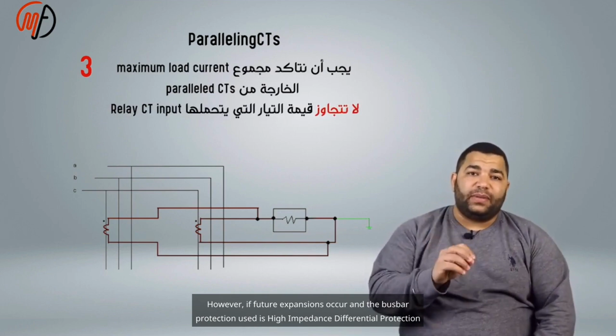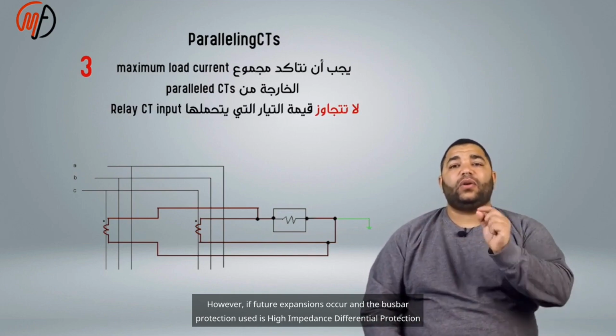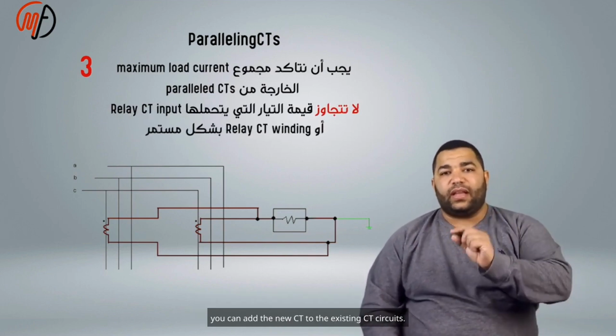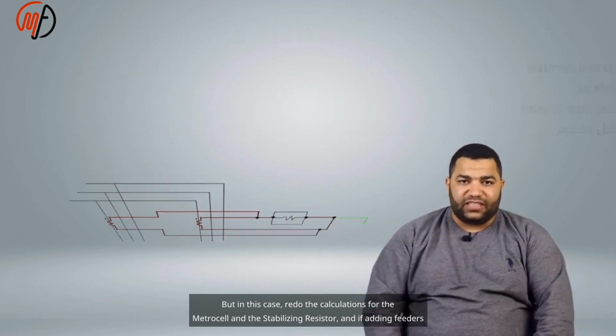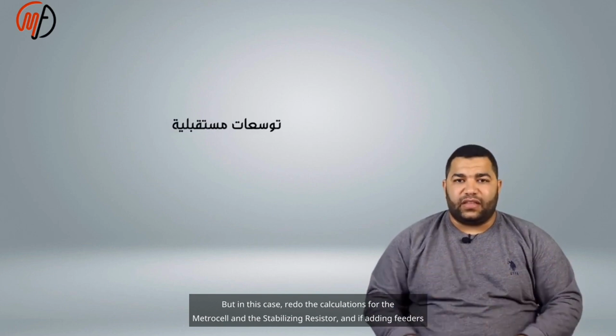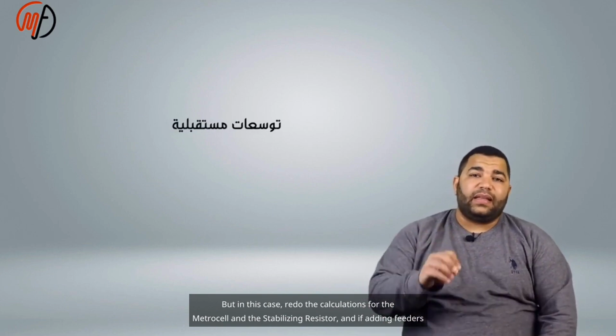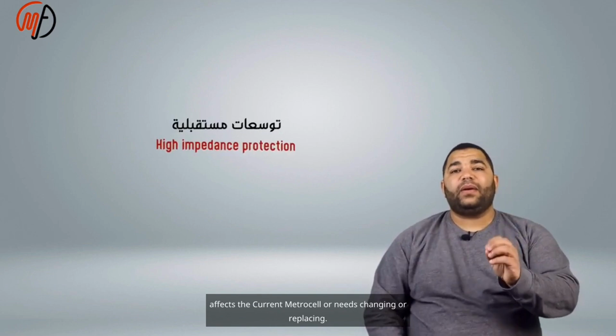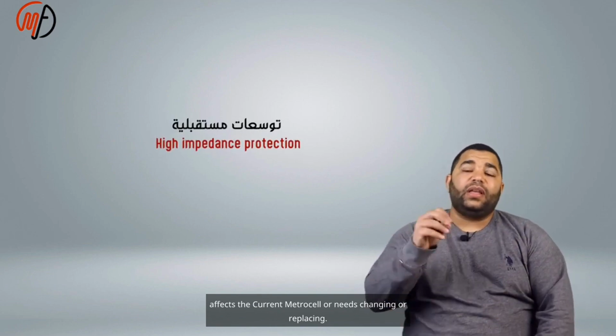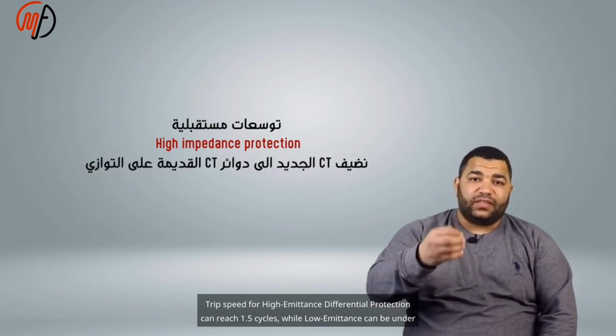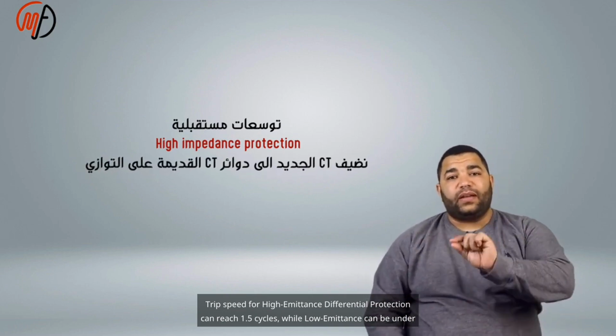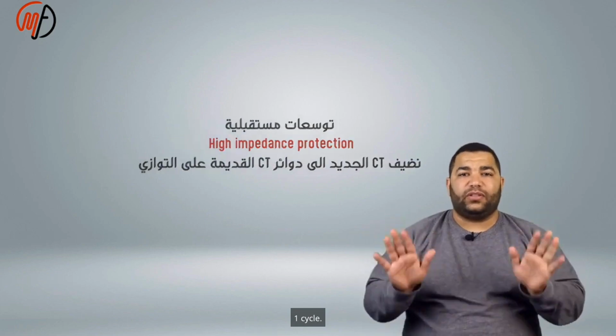However, if future expansions occur and the busbar protection used is high impedance differential protection, you can add the new CT to the existing CT circuits. But in this case, redo the calculations for the Metrosil and the stabilizing resistor, and check whether adding feeders affects the current Metrosil or requires changing or replacing it. Trip speed for high impedance differential protection can reach 1.5 cycles, while low impedance can be under 1 cycle.